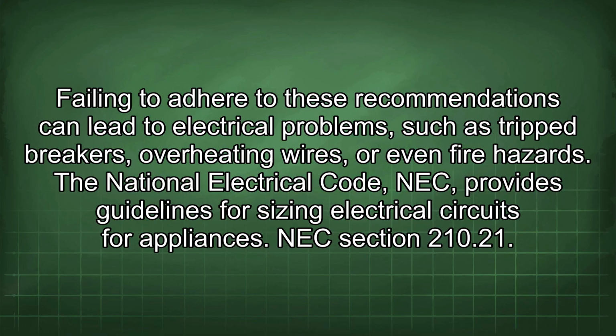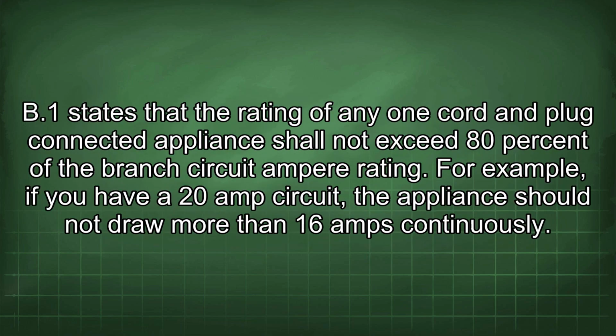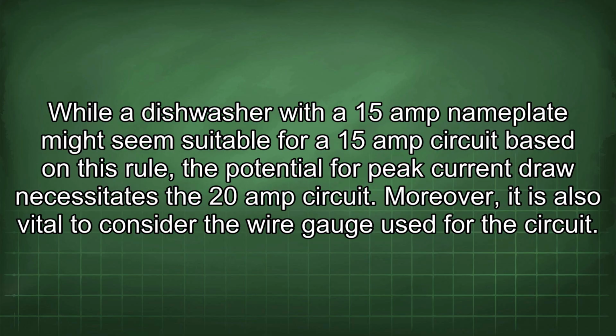NEC Section 210.21(B)(1) states that the rating of any one cord and plug connected appliance shall not exceed 80% of the branch circuit ampere rating. For example, if you have a 20-amp circuit, the appliance should not draw more than 16 amps continuously. While a dishwasher with a 15-amp nameplate might seem suitable for a 15-amp circuit based on this rule, the potential for peak current draw necessitates the 20-amp circuit.